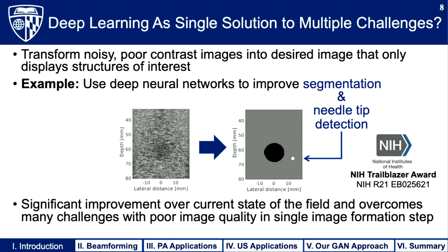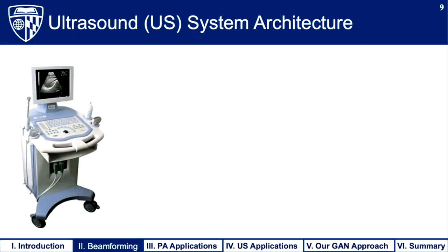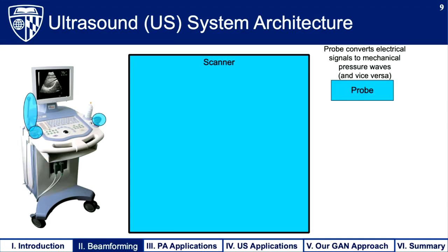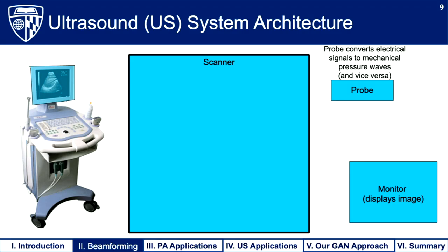Assuming you know a lot about deep learning, for the next part of the talk I'll go into more detail about the beamforming process. This is a standard ultrasound system used in the clinic. Its architecture contains three main components: the first is a scanner which houses much of the electrical components and the computing hardware; then we have a probe used to interface with the body in a range of different shapes and sizes depending on the body part being imaged; and then we have a monitor used to display the image on the screen.